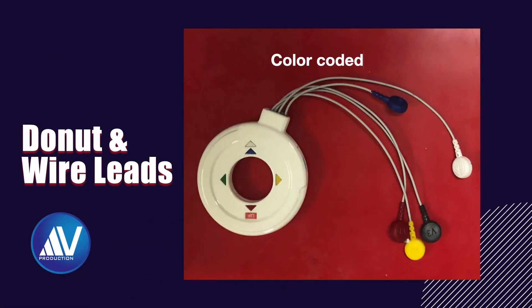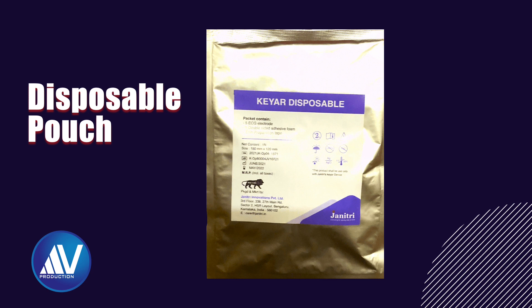This is a donut which has five color-coded wire leads coming out of it. Four have long wire leads. The fifth short wire lead is to be connected to the patch placed four fingers above the pubic symphysis, directly above the fetal head — equivalent to the fetal scalp electrode of intrapartum fetal monitoring. They have also introduced a new patch device that makes attaching lead wires easier, sold separately. The disposable pouch contains five sets of electrodes, exfoliation tape, and an adhesive ring sticker to be placed on the donut applied over the umbilicus.